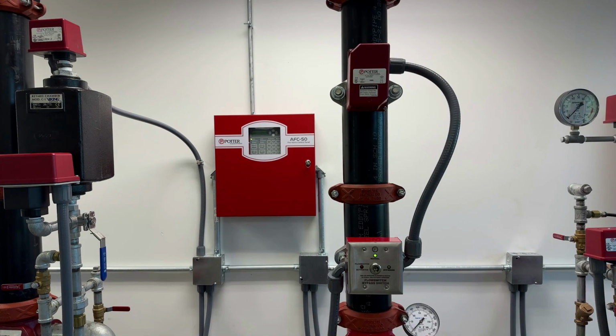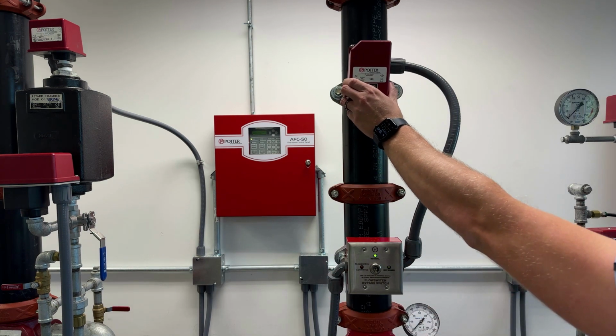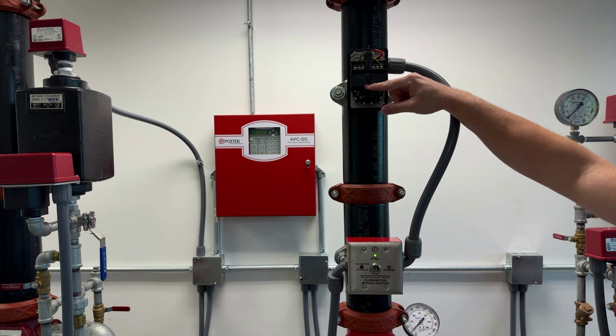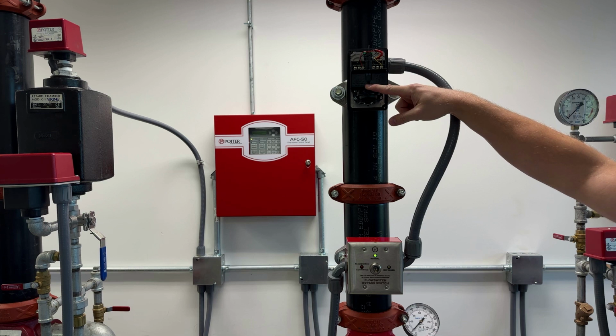When the FSBS isn't utilized and a system needs to be maintained or filled, traditionally the flow switch would activate and send an alarm signal to the fire alarm control panel. This would typically alert a central station and the fire department of an emergency event.